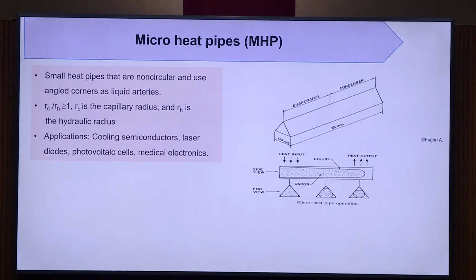Basically, there is a hydraulic radius. If the capillary radius is greater than 1, it will be considered a micro heat pipe. Applications are basically laser diodes, photovoltaic cells, and medical electronics. The heat load capability is roughly less than 5 watts, not more than 5 watts of heat load, and the length of the heat pipe is less than 50 mm.